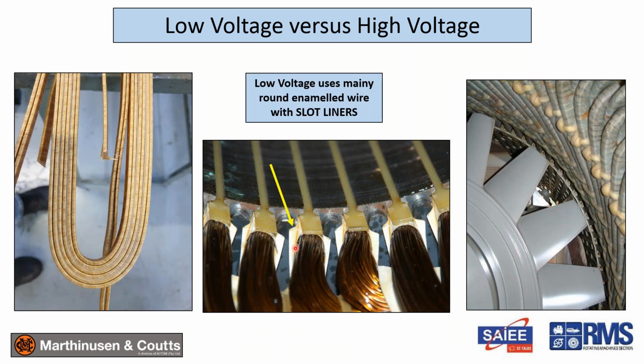Low voltage, I mentioned there, that same slide. You can see that there's the slot liner. You can have more than one slot liner. But in a low voltage machine, your strand insulation actually plays a fairly significant role in terms of the overall insulation.